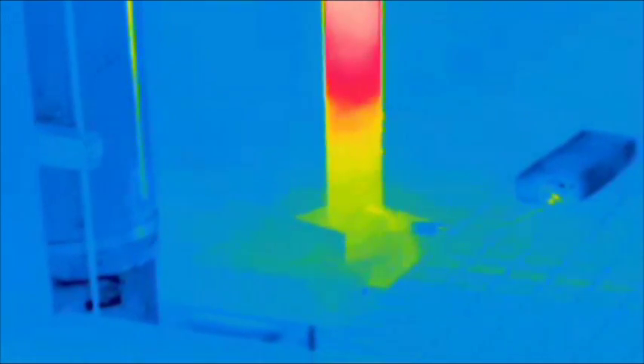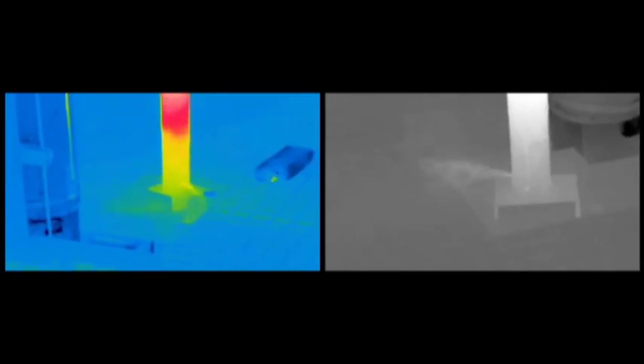Schiller has found leaks in unexpected places that would never likely have been found without an optical gas imaging camera. We found lots of gas coming into one of these junction boxes, and we were really surprised. It was a very unusual place to find gas because you never expect to see gas in the insulation. Also, we had one pipe support on a bend — they had welded this pipe support a little bit too tight, so the gas was leaking from the pipe into the pipe support and out at the bottom. They had tried before with the sniffer to find this leak because they could smell ethylene, but they could not find it with the sniffer.